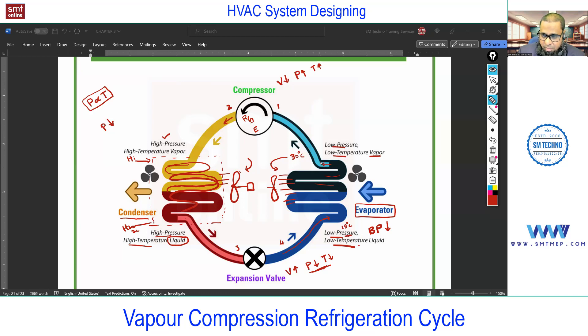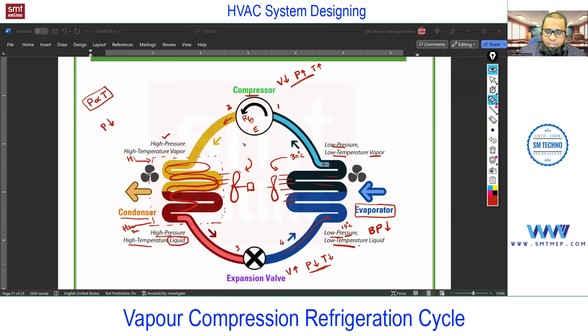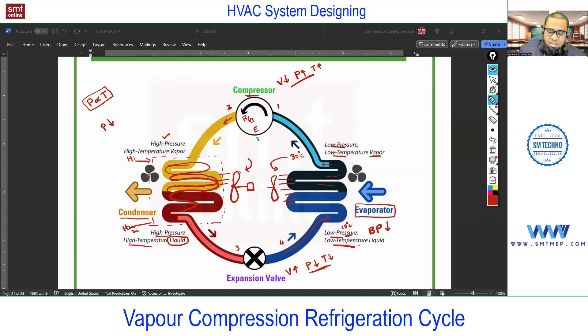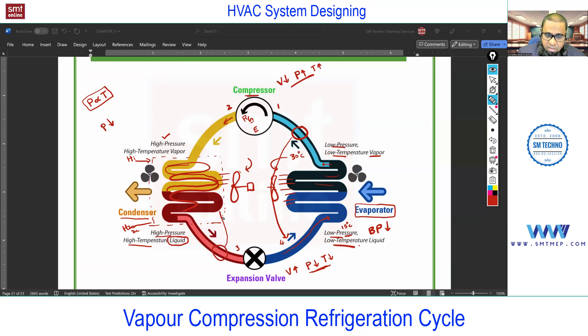At the outlet of the evaporator, the refrigerant condition is low pressure, low temperature, but in vapor state. In order to circulate again, we require the compressor. The low pressure and temperature vapor is sucked by the compressor, which again increases the pressure and temperature, and the cycle continues. In this way we get the cooling effect, which can be utilized for different applications. In actual practice you'll find an accumulator here, which will not allow any refrigerant liquid into the compressor — it bypasses it back to the circuit.